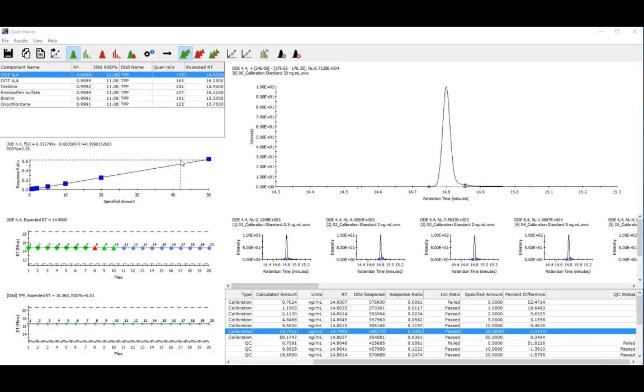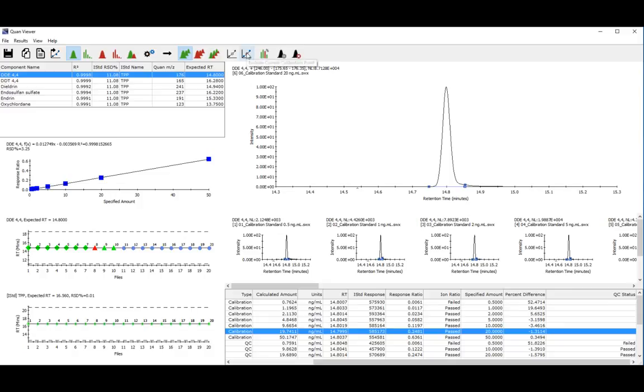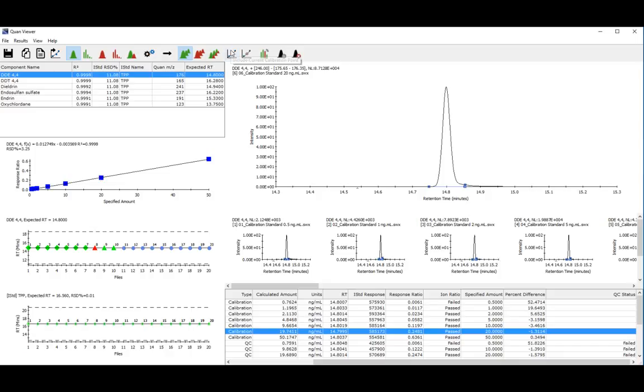Once you have reviewed your results, you can make changes accordingly. To exclude a calibration point, click on the point and then press Exclude Current Calibration Point. The point is now represented by a red triangle. To include the point again, simply click Include Current Calibration Point. When you exclude and include calibration points, your results are automatically updated.